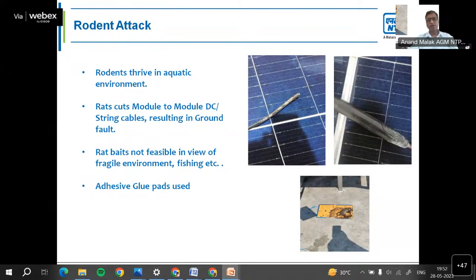This is rats biting the 6 square mm cables. Whenever they bite, the cables fall inside the water, creating a ground fault, which causes the inverter to trip. I will show a videograph so you can see how large the area is, and how difficult it is to identify which cable has fallen into the water.